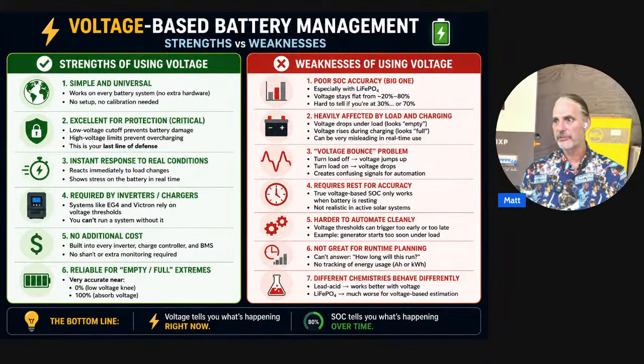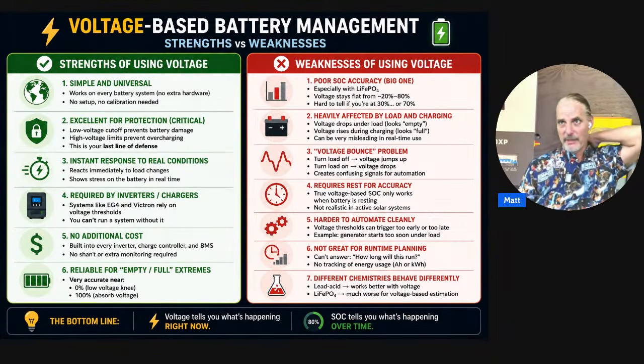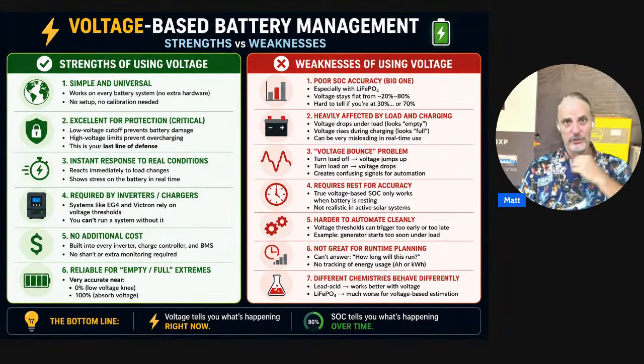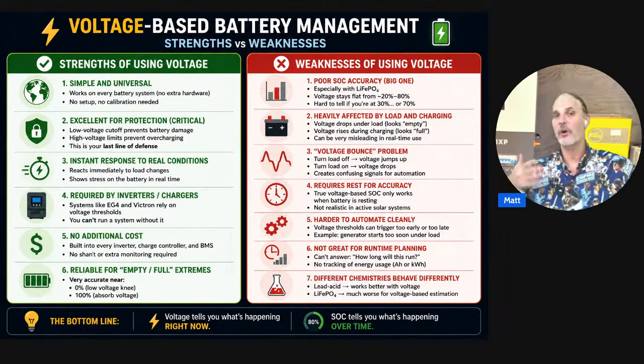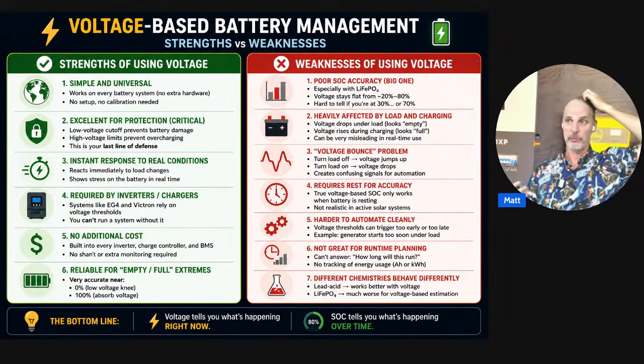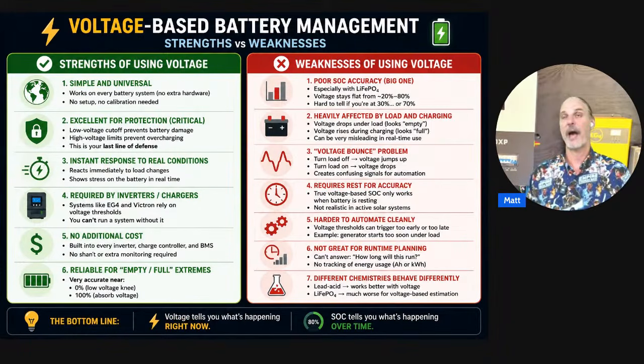Then instant response to real conditions - reacts immediately to load changes and shows stress on the batteries in real time. This one's really good also. It allows your system to respond, your charge controllers - a lot of the times I'll have, in addition to my 6000, Victron charge controllers or multiple charge controllers, and it allows them all to respond and help out with absorption and float, making sure there's enough power coming in even when my batteries are full, to supply all the loads.